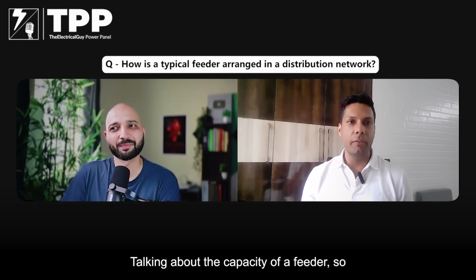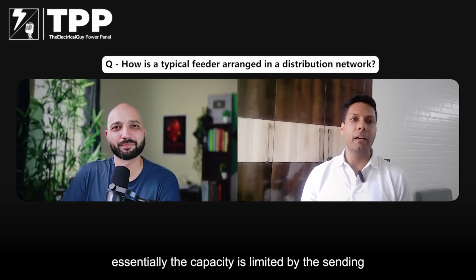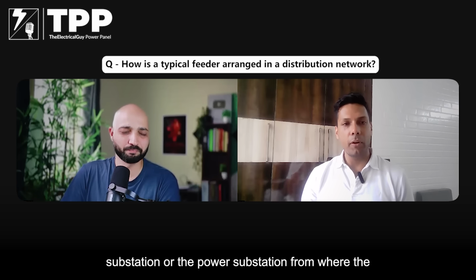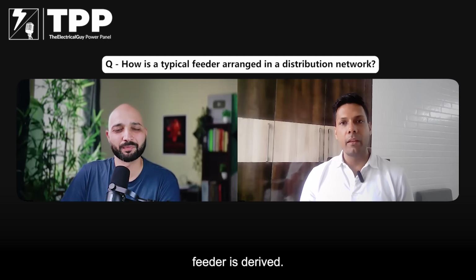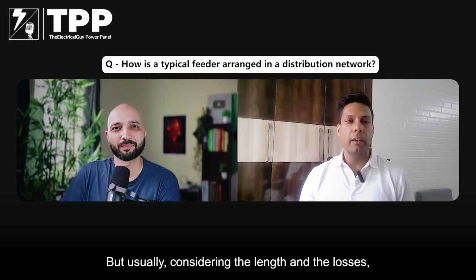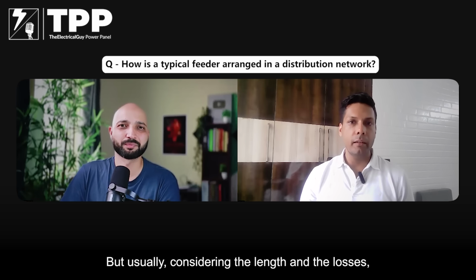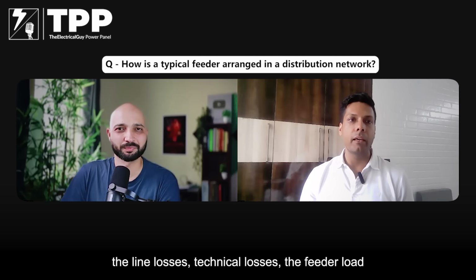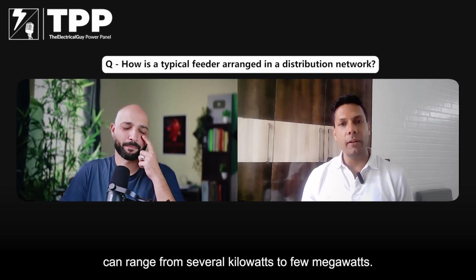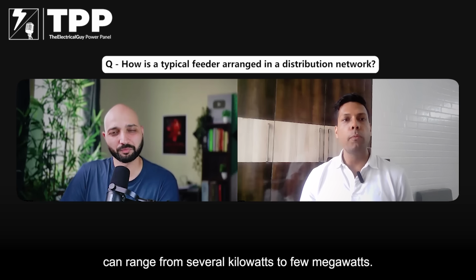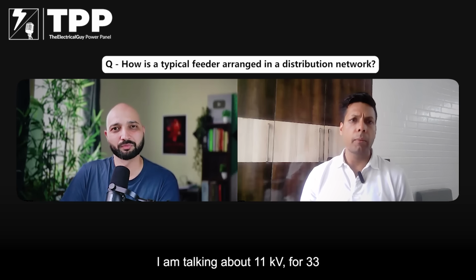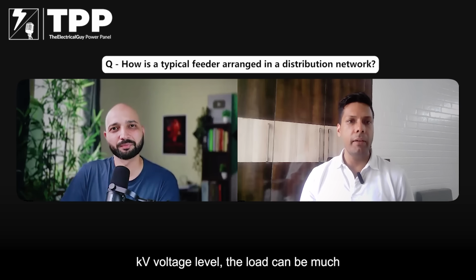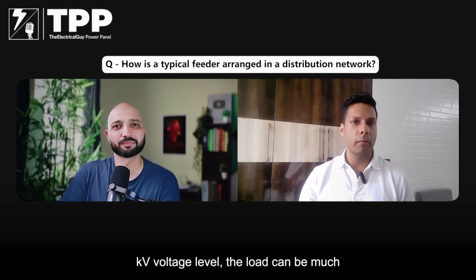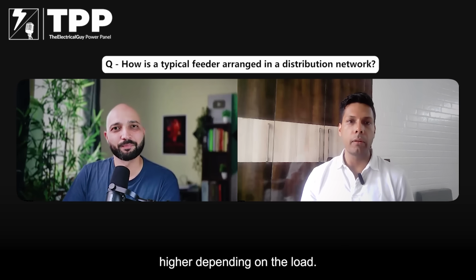Talking about the capacity of a feeder, essentially the capacity is limited by the sending substation or the power substation from where the feeder is derived. But usually, considering the length and the line losses, technical losses, the feeder load can range from several kilowatts to a few megawatts. I'm talking about 11 kV. For 33 kV voltage level, the load can be much higher depending on the load.